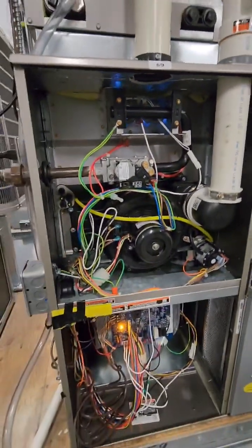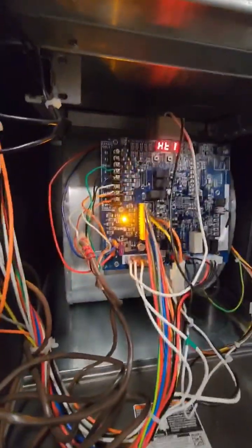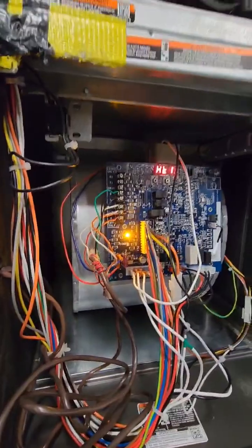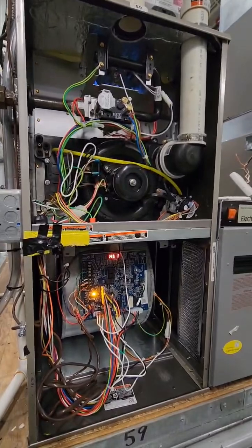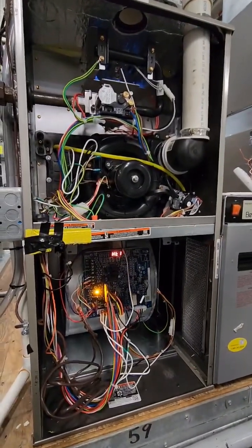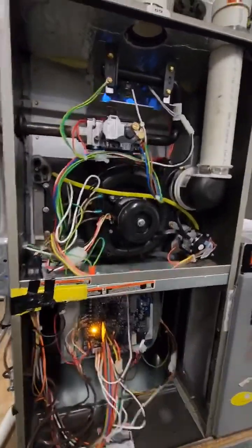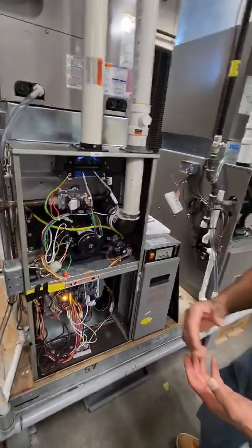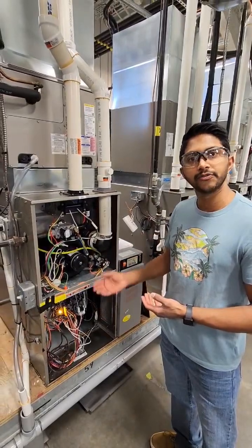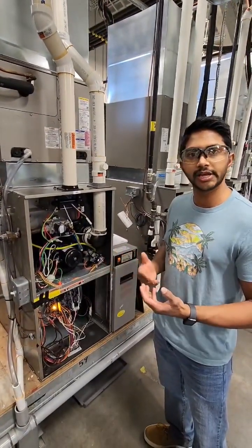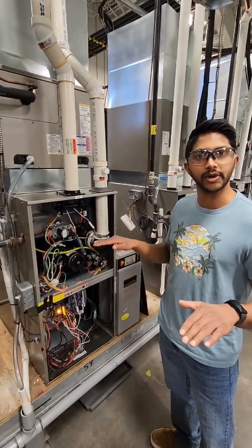The next step is going to be, once the desired temperature has been achieved, the blower motor will turn on and will begin to circulate hot air throughout the home and the duct system. Once the thermostat has been satisfied, or in other words, once the appropriate heat has been reached, the gas valve will de-energize, and then the sequence will go in reverse. The blower motor will stay on for a specified time delay, usually around 30 seconds to 1 minute. Once the heat exchanger has cooled down, the blower motor will shut off, and the system will go back to rest. And that's it.